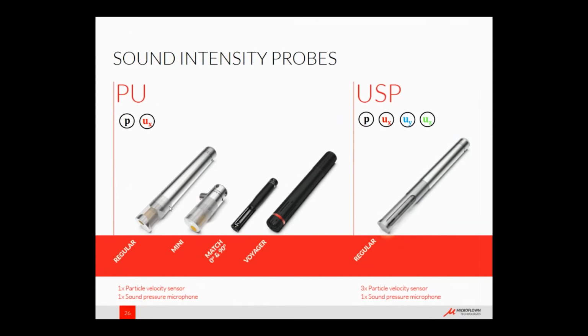The mini, for array applications, to use multiple of them closely spaced. The match, which is really the smallest sensor of them all. The Voyager, which is designed as a robust probe to take outside the lab into the field. But all those probes, in essence, carry the same core technology, one direction particle velocity with a sound pressure mic. So we can use it for particle velocity measurements, sound intensity measurements, sound power measurements, absorption measurements.